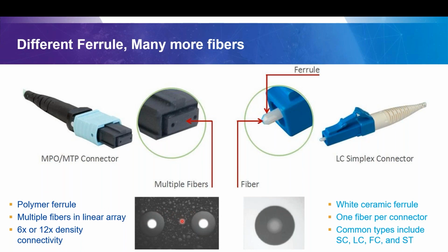But just keep that in mind when you look through an inspection probe at the end face of these MPOs. That's what you're going to see, and it's not dirt. It's just a different material.